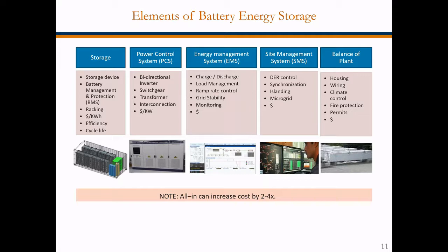The system is broken up by modules or racks—I shouldn't say stacks, since that gets confused with flow batteries—but you have cells within trays, within modules, and racks of cells, and all these cells need to be managed. The battery management system looks at all those cells, making sure there's no over-temperature and that they're all at the same charge level, et cetera.